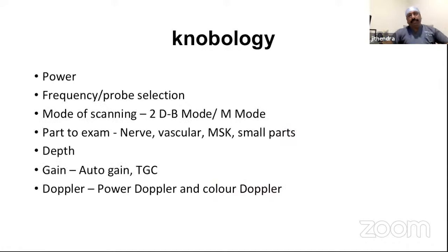Before starting ultrasonography for any procedure, you need to know something about knobology. The first and foremost thing is switching on the ultrasound machine with the power button. Next, you have to select the probe to be used. As I said, for superficial structures you go for the linear probe for better resolution. For deeper structures, you go for the curvilinear probe. And for echo, you need to use the phased array probe. Then you select the mode of scanning, either 2D mode, B mode or M mode, depending upon what you want to identify.